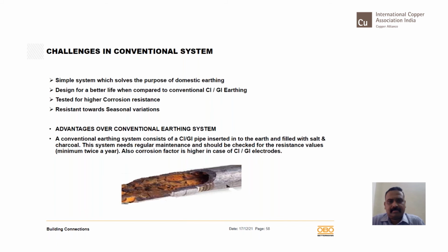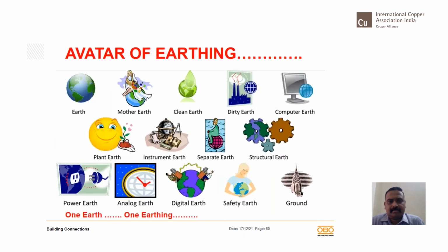And remember, your resistance is obtained only with the resistivity that you achieve by going deeper into the ground. For example, if you insert 3 meter or 6 meter, the soil resistivity at that level will be your resultant resistance which you obtain at the body equipment level. So if this electrode is disconnected, you may not be able to tap the least resistivity point below. So this kind of system had a problem in adding salt and charcoal to it. And that is why people practiced copper bonded earth electrodes and then added chemical compound to it to avoid that kind of damage.